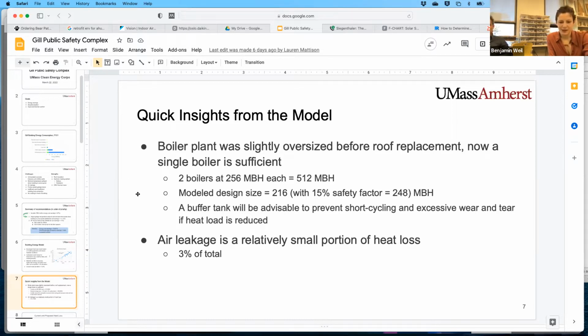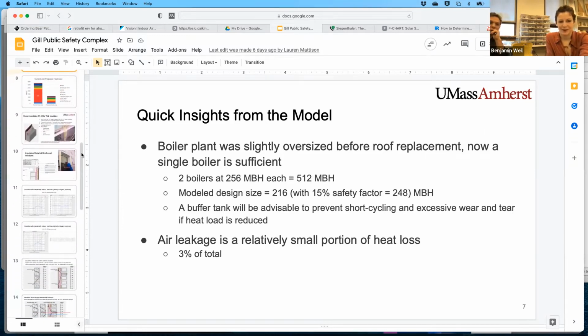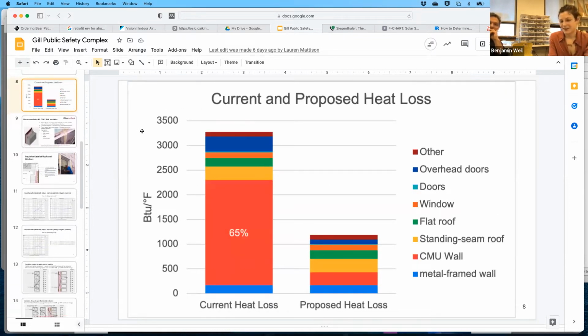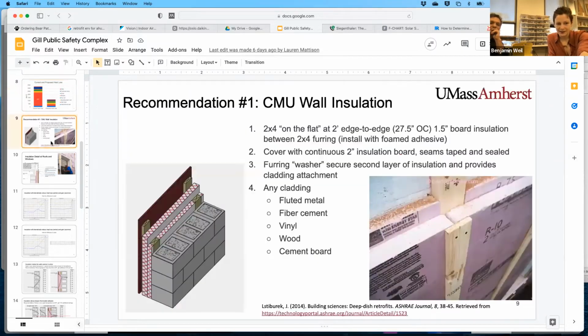We also found out that because there's such a tremendous amount of conductive heat loss going on through these CMU walls, air leakage actually is proportionately a pretty small amount of the heat loss. So it's about 3% total. So insulating the walls is really the big ticket item here when it comes to energy conservation. And here's an illustration of exactly how that plays out. So here's a representation of what each assembly contributes to heat loss before and after the proposed changes. And here's how we recommend doing that.